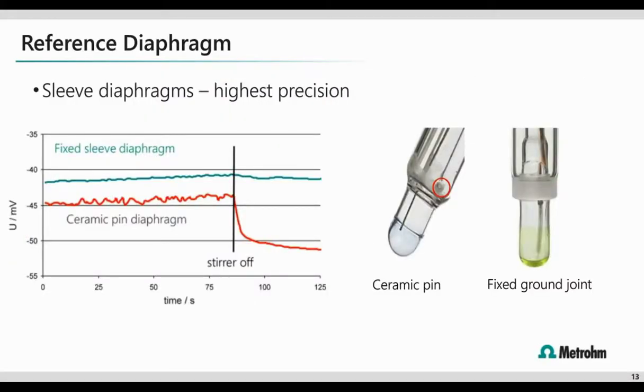Just like the membrane bulb, you may notice a couple of different designs for the diaphragm. The ceramic pin may be considered a little bit more of an older generation, so that's the electrode image on the left. You see a very tiny red circle around that pin diaphragm. For the most part, the fixed ground joint, or the electrode to the right, is more commonly what you'll see.